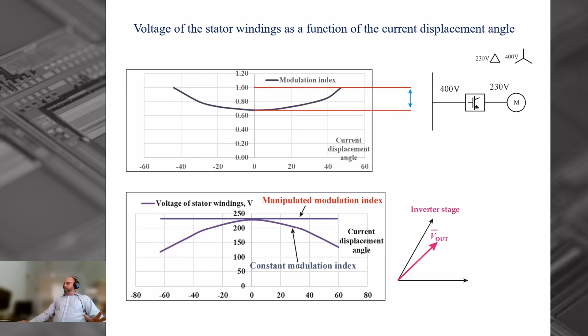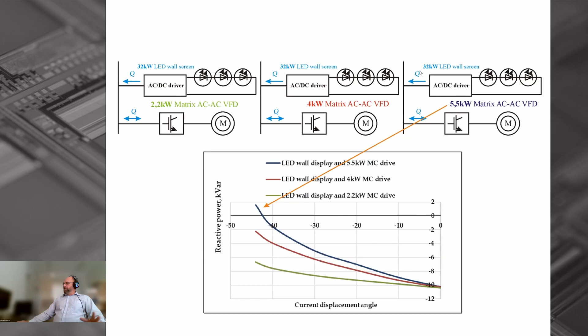The simulation results show that by using a 5.5 kilowatt matrix converter based variable frequency drive, it could compensate the reactive power produced by a 32 kilowatt LED lighting device.